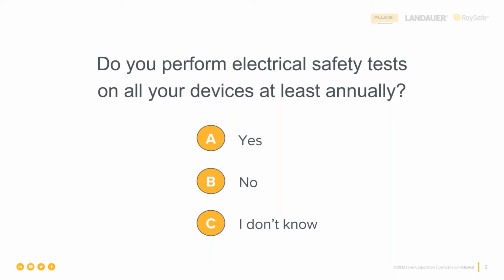Also, anytime you do a repair on a medical device yourself in-house, then you also need to do another electrical safety test with measurements to make sure that you have returned that medical device to being safe and effective for clinical use.